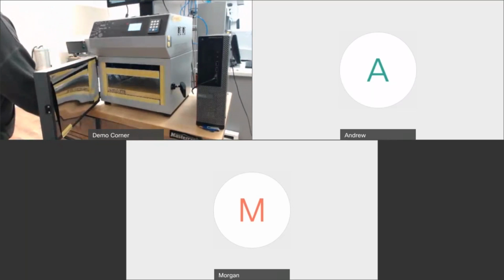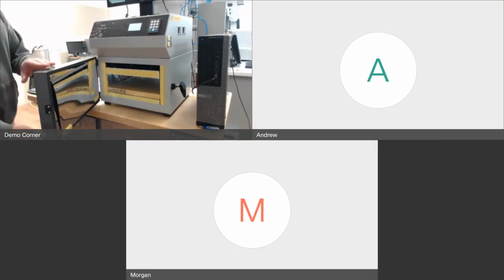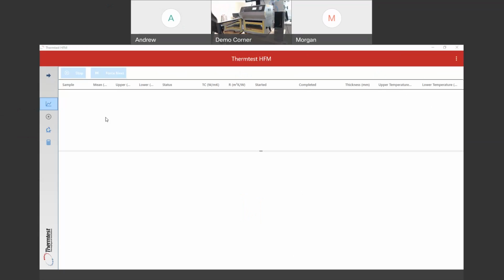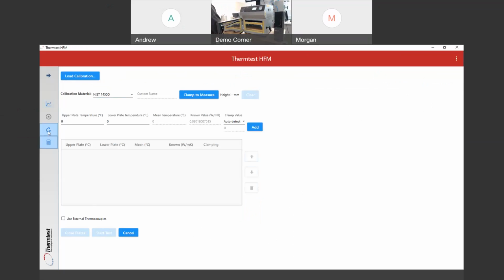And then I'm going to share the screen again. You zeroed it. Now we're going to calibrate it. Now we can calibrate it, and it would be almost identical if you're going to test. I'll show you the difference. Here, this calculator is your calibrate, and the microscope icon is your test, but we're going to calibrate. So there's 1450D. If in fact I had 1450E, I would select that one. All it is doing is pulling from the calculation that you get on the certificate. If you've ever done that in Excel, we've done that for you so that when you put in the upper plate, let's say you're going to do 20 degrees average, you're probably doing a 20 degree delta. That's what we typically do. And your mean is 20, so it's automatically calculated and pulled into the to-be-run schedule.